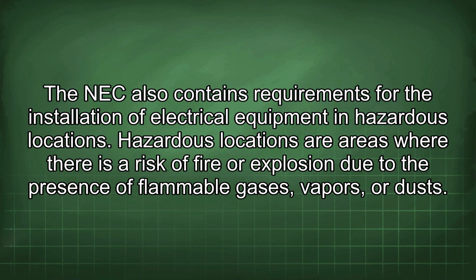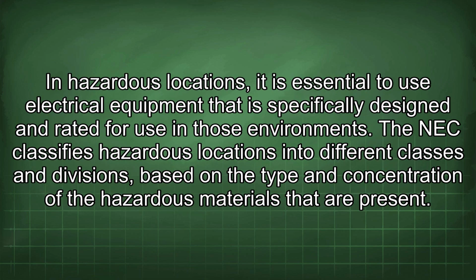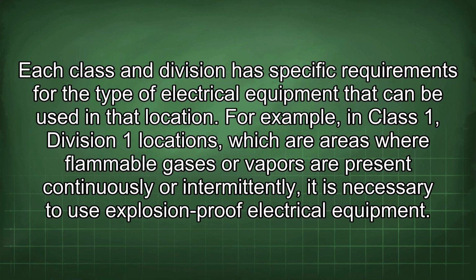The NEC also contains requirements for the installation of electrical equipment in hazardous locations. Hazardous locations are areas where there is a risk of fire or explosion due to the presence of flammable gases, vapors, or dusts. In hazardous locations, it is essential to use electrical equipment that is specifically designed and rated for use in those environments. The NEC classifies hazardous locations into different classes and divisions based on the type and concentration of the hazardous materials that are present. Each class and division has specific requirements for the type of electrical equipment that can be used in that location.